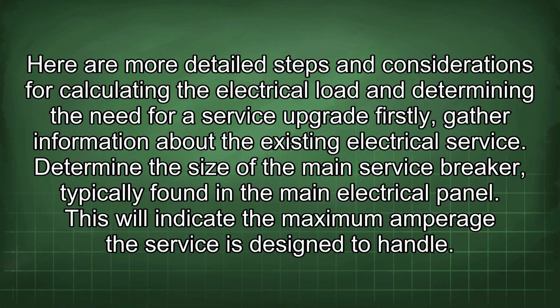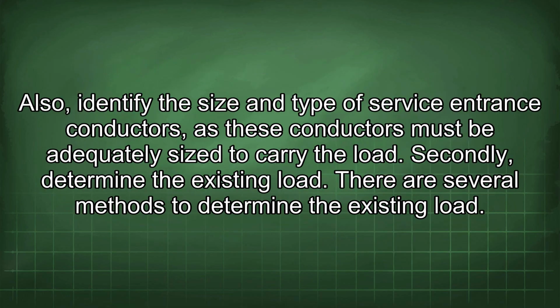Firstly, gather information about the existing electrical service. Determine the size of the main service breaker, typically found in the main electrical panel. This will indicate the maximum amperage the service is designed to handle. Also, identify the size and type of service entrance conductors, as these conductors must be adequately sized to carry the load. Secondly, determine the existing load.